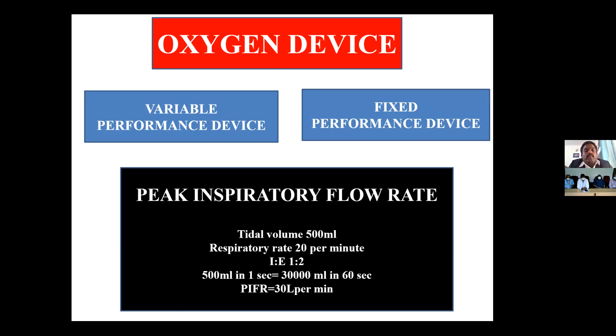And the ones which don't give this, it's less than that, those are low flow devices. And the high flow devices give a fixed oxygen, whatever FiO2 we set, that amount of FiO2 is delivered to the patient. They are known as fixed performance devices. And when it is less than that, it is a variable performance device. So depending upon the patient's demand, depending upon the peak inspiratory flow rate, the oxygen devices are divided into fixed and variable performance devices.